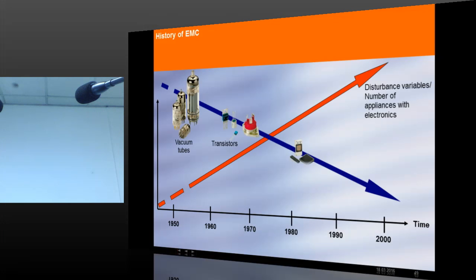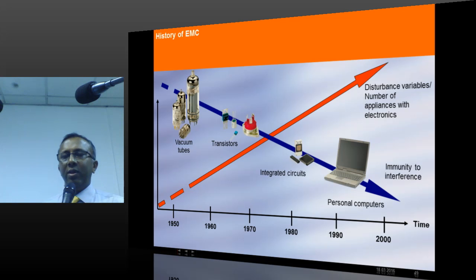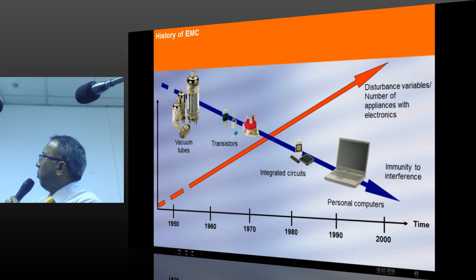Why has surge protection become important now? Because the disturbances in our network are increasing day by day. On the other side, this picture shows that in the early 1950s we were using vacuum tubes. That means there was enough space between two terminals, more insulation, it could withstand more. Whereas now we go for large scale integration, very large scale integrated circuits where the insulation levels are very low. So since the disturbance is more and insulation levels are very low, you need surge protection.